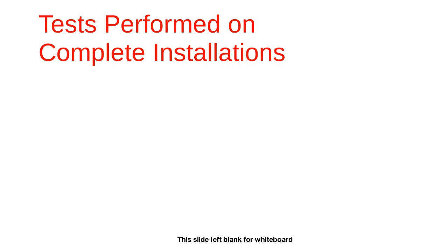The other thing to check are the warning notices. What do you mean by this? You have seen around, even where you are, if you're in a commercial building, those notices that are usually labeled around. Like in a lift, you see a notice saying high voltage, do not touch, do not operate if you're not a technician. Those are the notices that we're talking about. So the warning notices are a factor to consider under visual inspection.